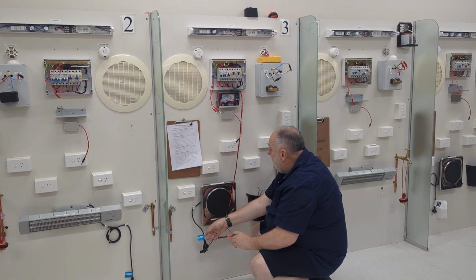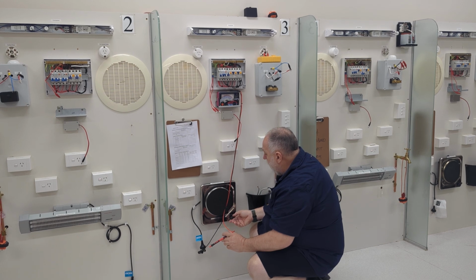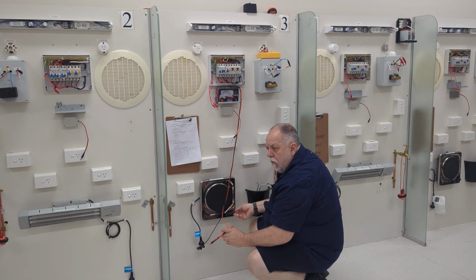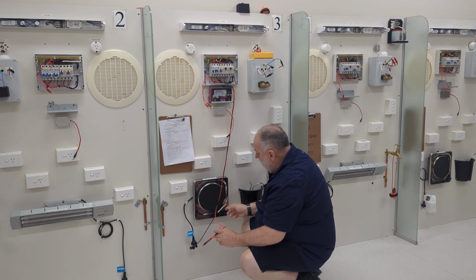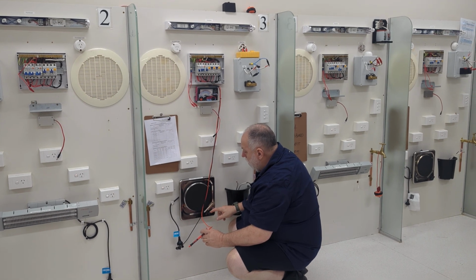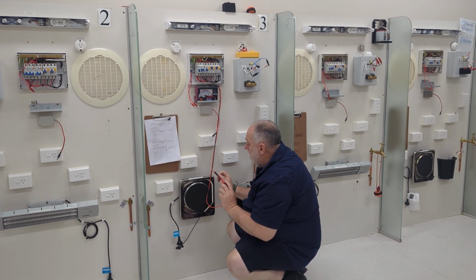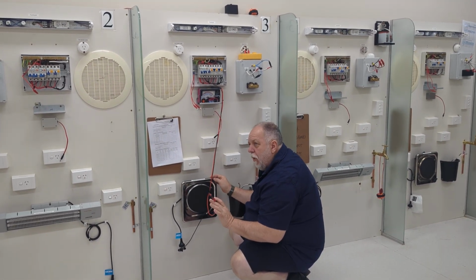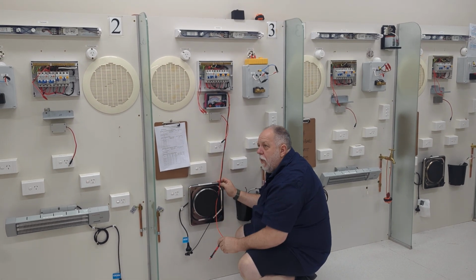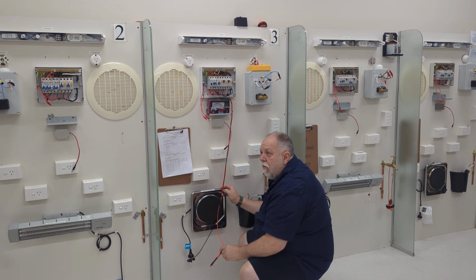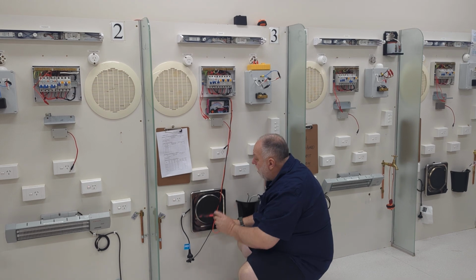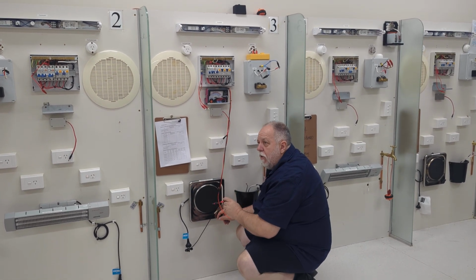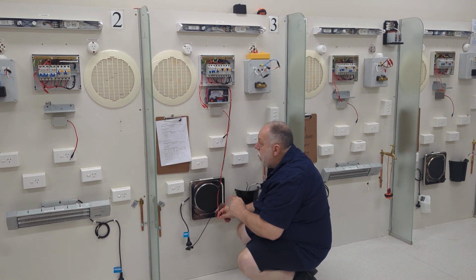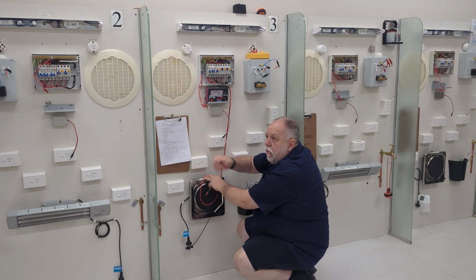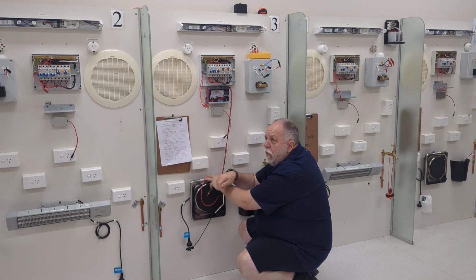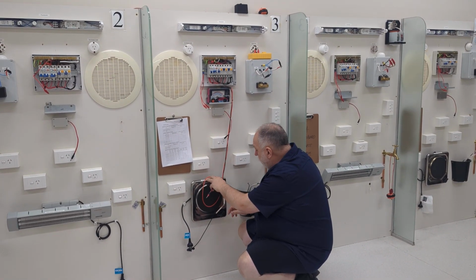Now, the next point, I need to make sure, can everybody hear that clicking? Hang on a second. Yeah. One thing, I'm not sure, but in the SWP, I've heard that they get an indication when that thing's turned on. All right, so make sure you turn it on. Before you do any testing or checking on your appliance in the SWP, turn everything on. Same with the strip heater, 1, 2, turn it on up to high. Don't just turn it on to the first one. You must turn everything on to full value.